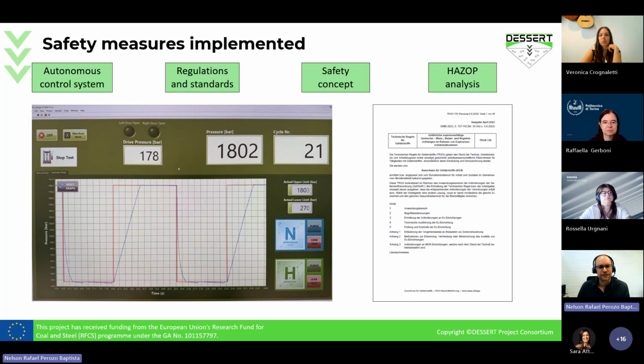And finally, we have the design of an autonomous control system, which is in charge not only of controlling the test, the automatic application of pressures and loads, but also reacting in case of deviations of the parameters during the test, and also in case of leakages.